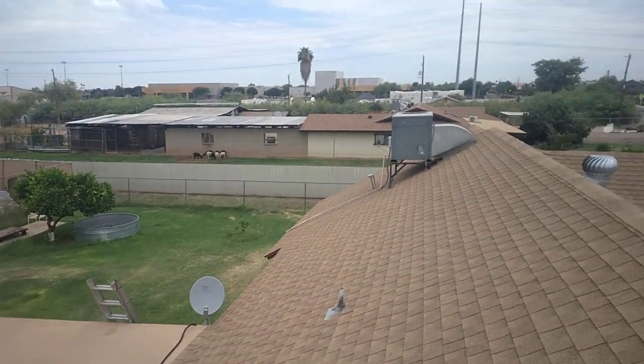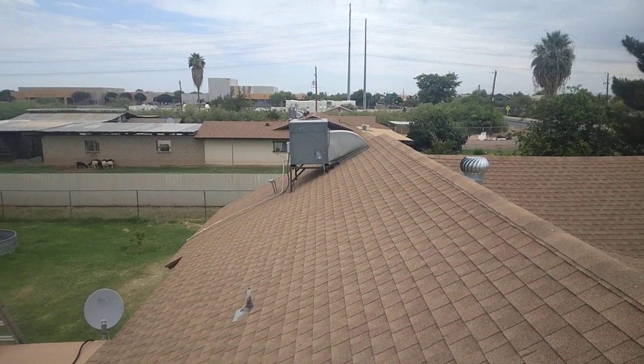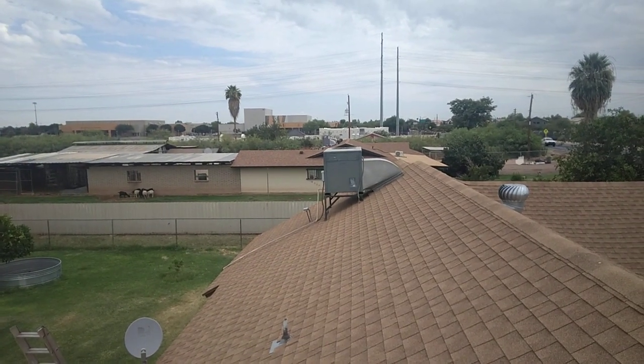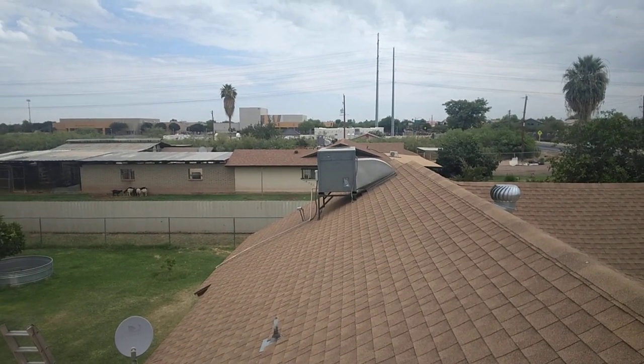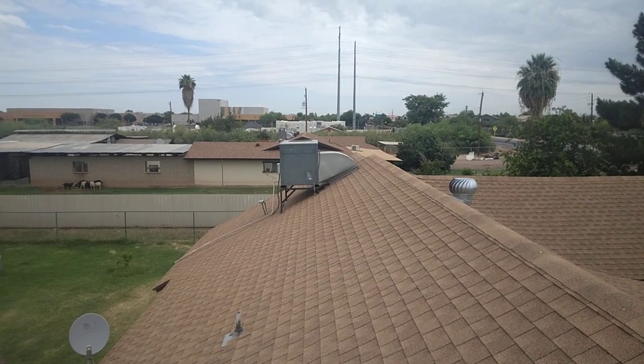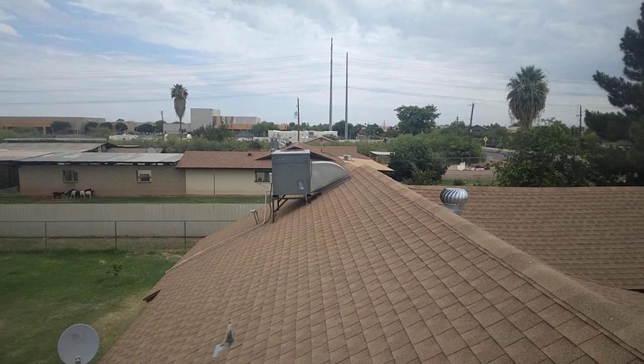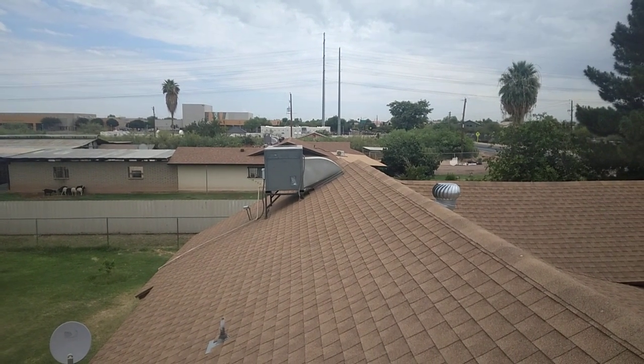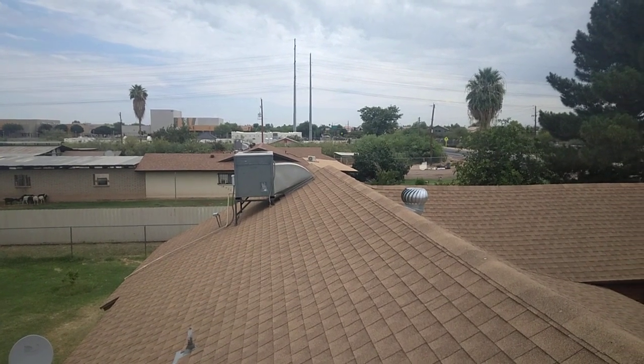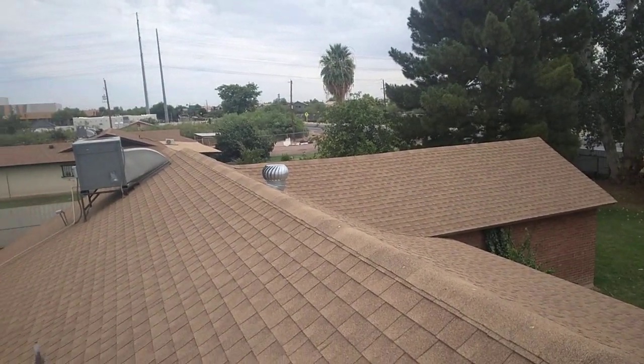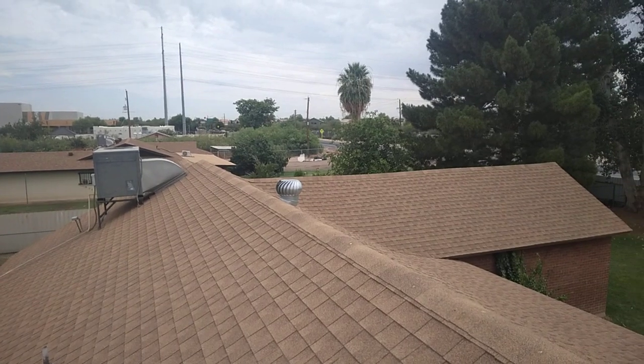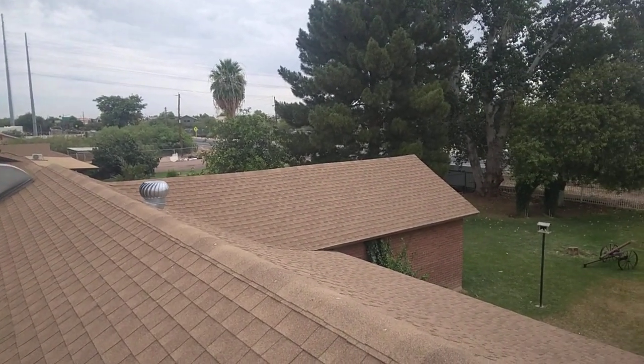There's my ladder, there's the unit I replaced the reversing valve in. And the inside coil, man, that thing was massive dirty. I'm thinking they bought the unit used with that coil dirty because the filter was good, and I'm not sure quite, but maybe there were bad leaks in the ductwork. I don't know, but anyway that's what's there. I'm not surprised that thing was icing up as dirty as it was.